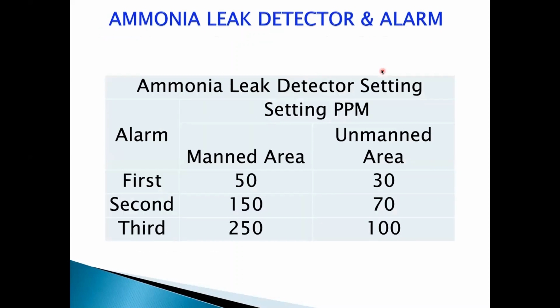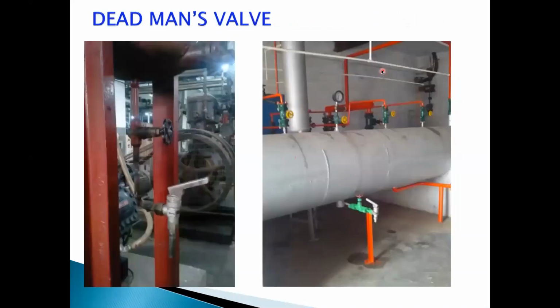These are typical recommended settings depending on manned area or unmanned area. Like inside the cold storage, there may not be people, so there has to be a very low level of setting. Whereas in the plant rooms, there are people and sometimes they smell the ammonia, so you can have higher operating settings. That depends on company to company, and some companies even have the alarm at 10 ppm.